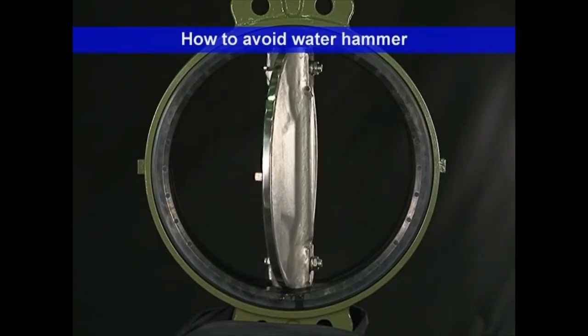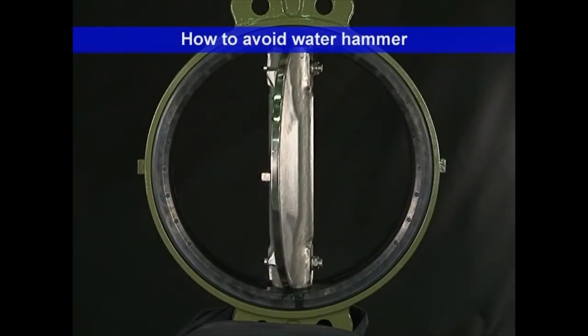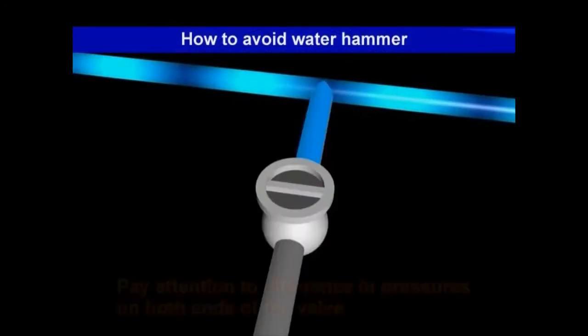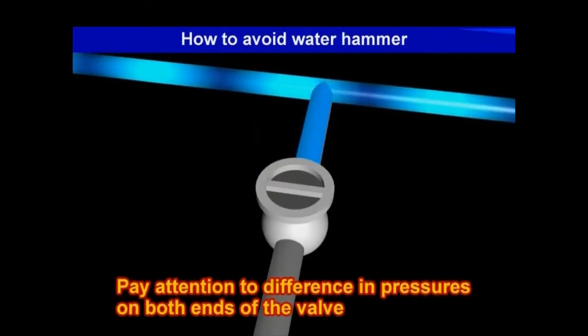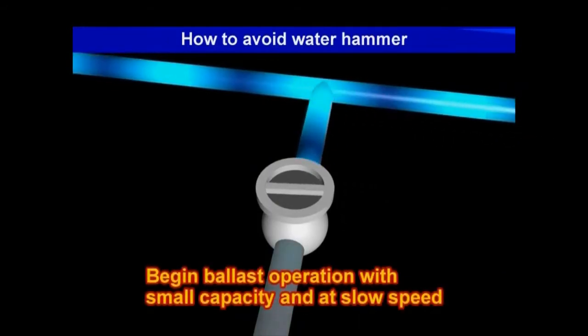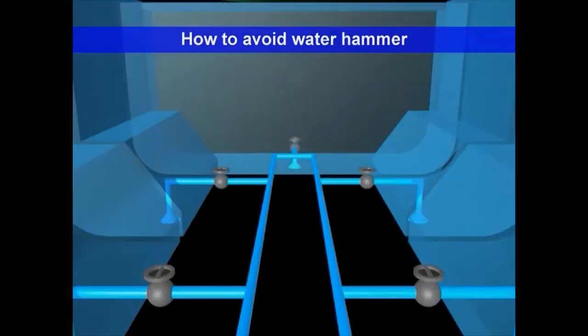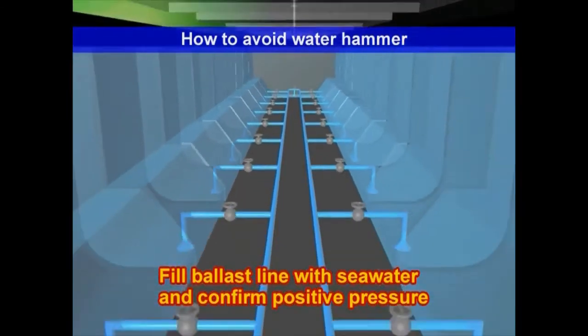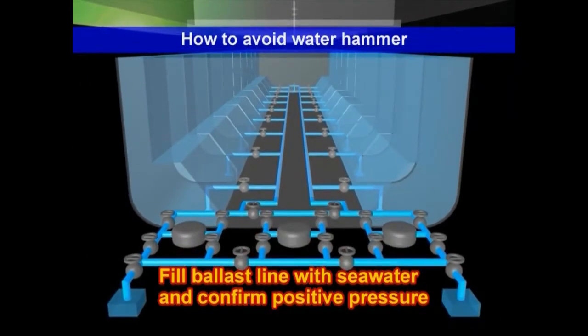In addition, general points to remember for avoiding water hammer are as follows. Pay attention to the difference in pressures at both ends of the valve. Begin ballast operation with a small capacity and at a slow speed. Fill the ballast line with sea water and confirm that the line has positive pressure.